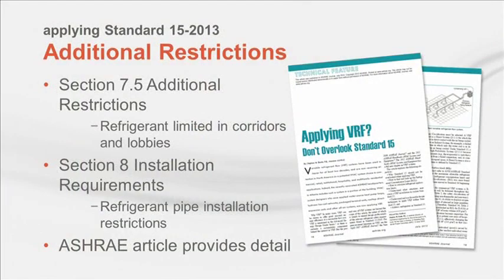In addition to RCL, there are other requirements of Standard 15 that apply to VRF systems. For example, there are restrictions on refrigerant use in corridors and lobbies, and requirements for the installation and location of refrigerant piping. These requirements also apply to single evaporator split systems, so you might already be familiar with them.